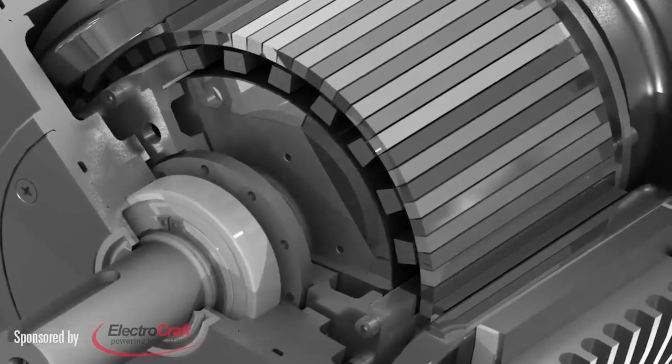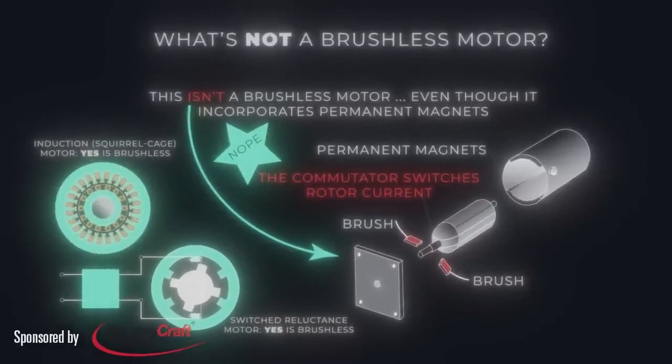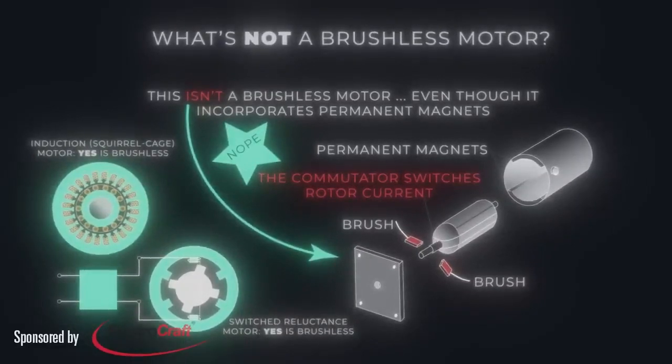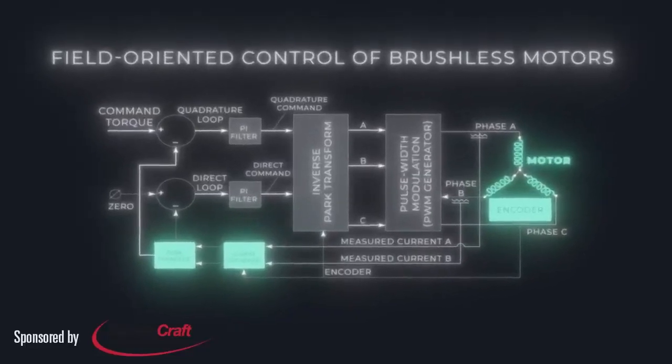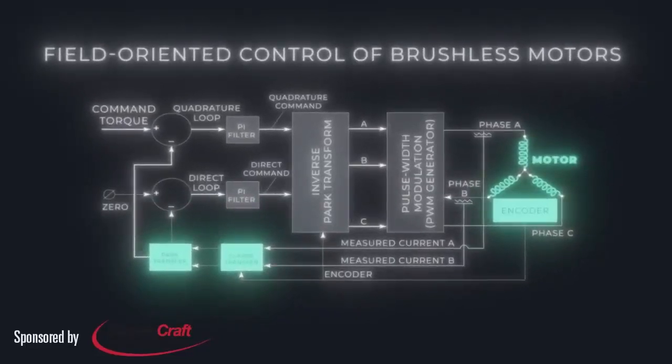Note that there are some naming convention caveats. There are permanent magnet motors with brushes for mechanical commutation, and these are commonly called PM DC motors. Brushless DC motors have permanent magnets, so they're technically synchronous motors, but run off AC from a DC bus and electronic inverter.